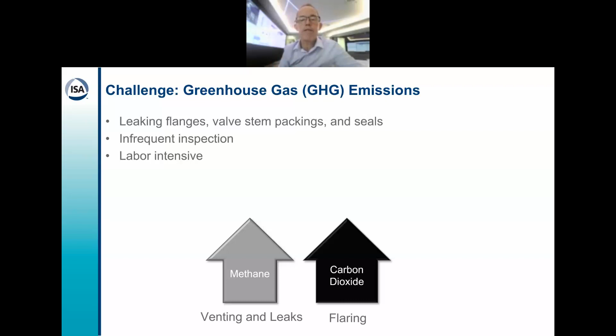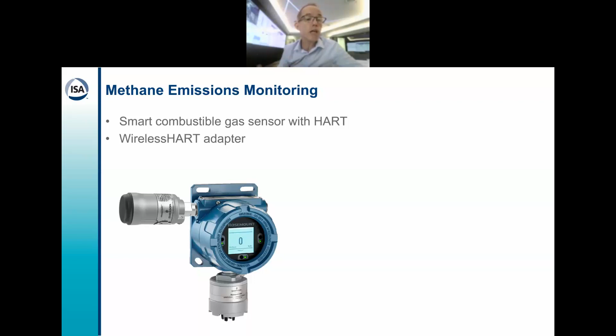A wired 4 to 20 milliamp smart combustible gas detector can be used for methane detection. It can be fitted with a wireless HART adapter, just like wired flow meters, to enable wireless transmission of measurement data and for configuration and diagnostics as well. Again, one of the reasons why wireless HART is so popular in plants is because it supports these HART adapters, which most other wireless sensor network technologies don't.